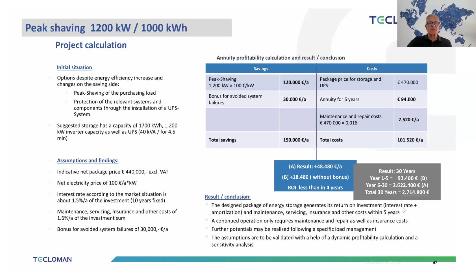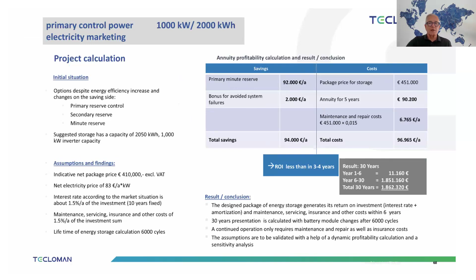In the same year, purely through primary and secondary reserve control, that is frequency stabilization and grid support, you see here for a storage system costing 451,000 euros, they got around 94,000 euros because of this regulation from the grid companies. So only because of this, without any arbitrage, the return on investment was achieved in 4 years.